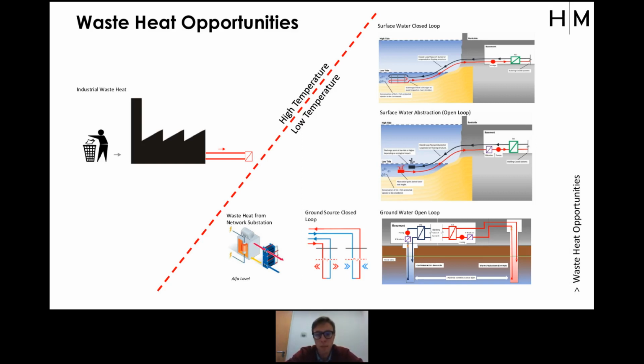So backup by a water-to-water heat pump connected to a relatively consistent heat source would help you improve your efficiencies annually. And another thing to consider, if you're looking at a 4th generation system and trying to minimize your additional heat pump requirements, is having a water-to-water heat pump connected to a low grade or low temperature heat source into the system. You could also integrate only directly into higher temperature systems.